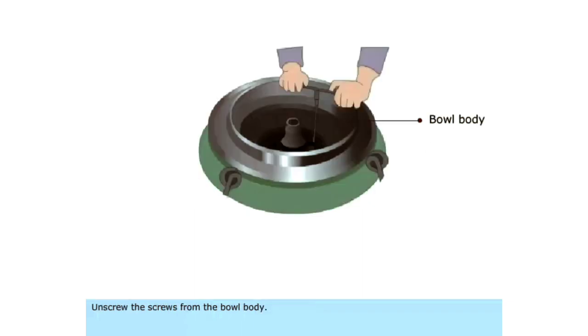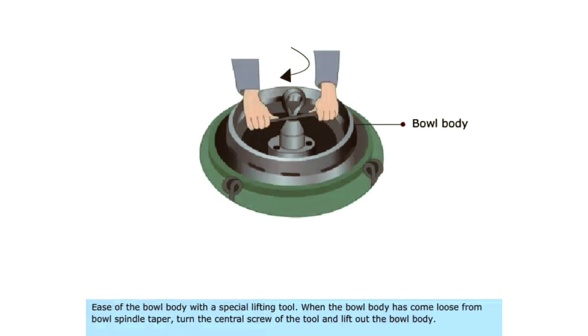Unscrew the screws from the bowl body. Ease off the bowl body with a special lifting tool. When the bowl body has come loose from bowl spindle taper, turn the central screw of the tool and lift out the bowl body.